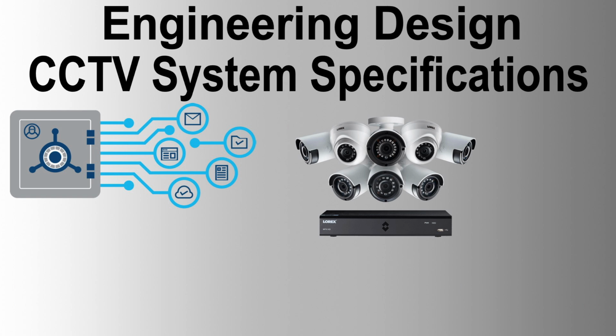Inspection and testing. All CCTV system equipment and components shall be tested in the manufacturer's works. The vendor may be required to carry out any or all tests stated in this specification under the witness of the purchaser or its representatives. Testing and factory acceptance tests, FAT, of the CCTV equipment shall be performed in line with this specification and in accordance with relevant project documents and international standards as the minimum requirement. Acceptance by purchasers' representatives of any CCTV equipment shall not relieve the manufacturer from any of his obligations.